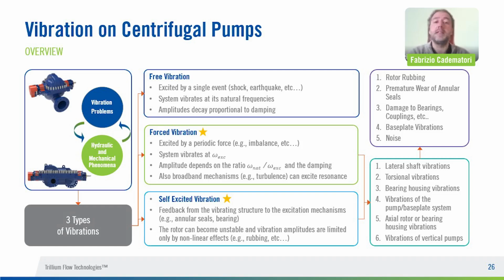For an analyst, it is fundamental to understand the interaction between hydraulic and mechanical phenomena. We can mainly differentiate three different types of vibration. Free vibration occurs when a single event excites the system, which then vibrates at its natural frequency with an amplitude that is proportional to damping. Forced vibrations are generated by a periodic excitation force, then the system vibrates at the forcing frequency, and the amplitude is a function of damping and the separation margin between excitation and natural frequency of the system.